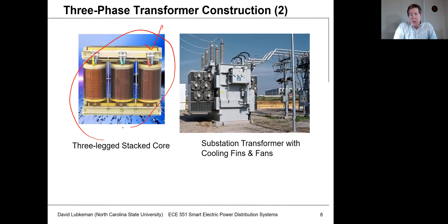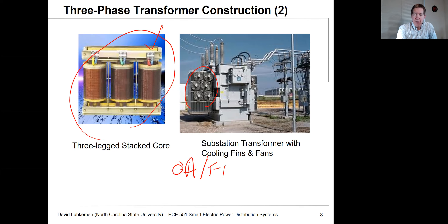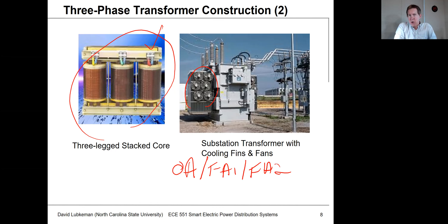It's fairly inexpensive, and when placed in a tank, you can cool the windings as current flows through them and I-squared-R losses develop. The image on the right shows a utility or large industrial three-phase transformer application. Something to note are the cooling fans. A large unit will often have an OA (oil, air natural) rating, and then additional ratings depending on whether one or both sets of fans are running — the fans cool the circulating oil, increasing the effective rating of the transformer when switched on.